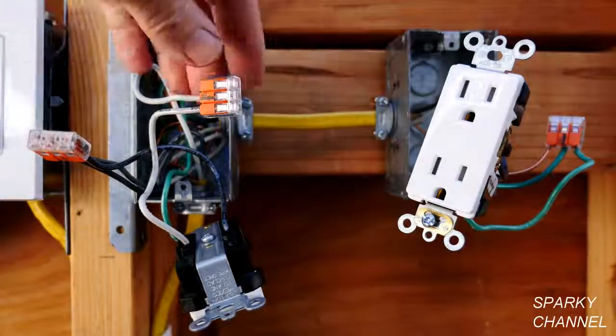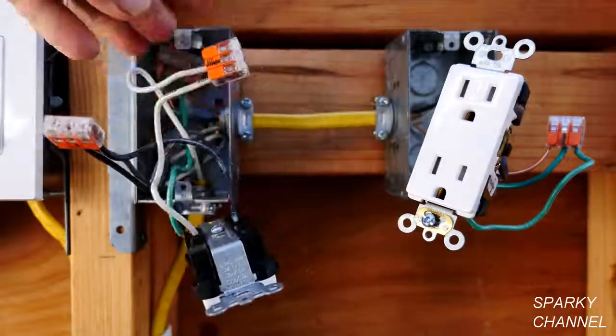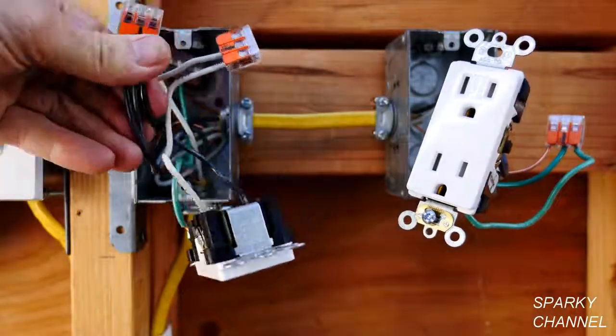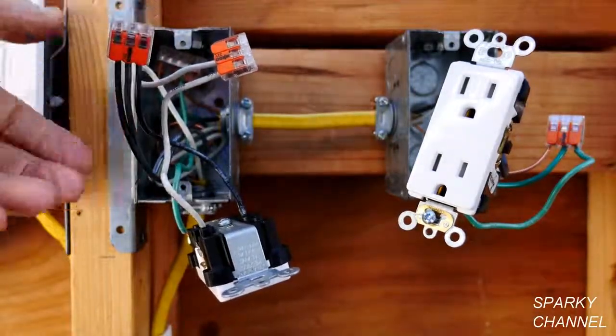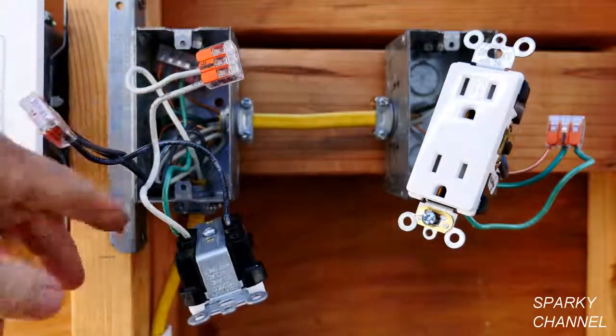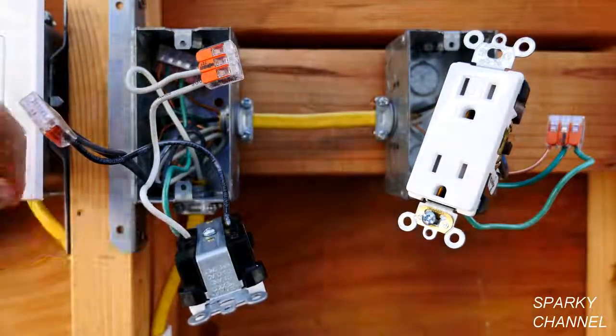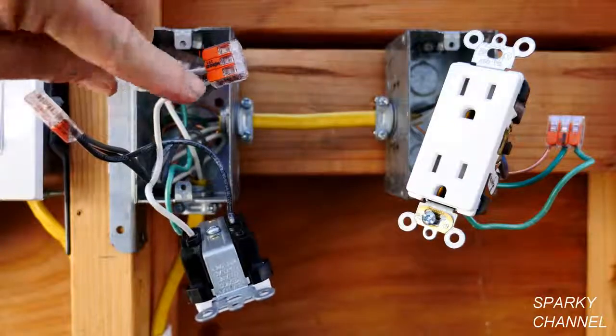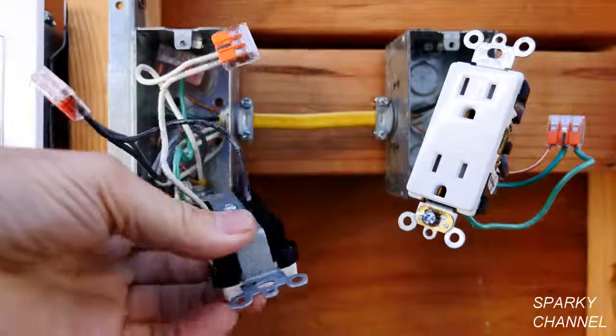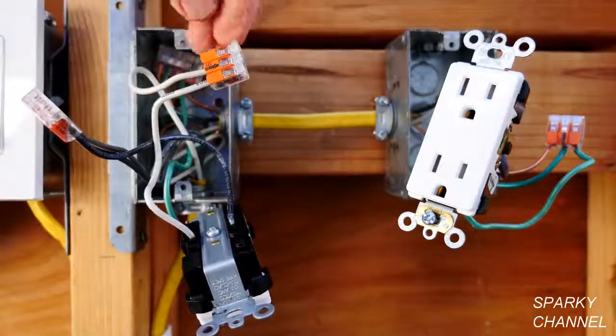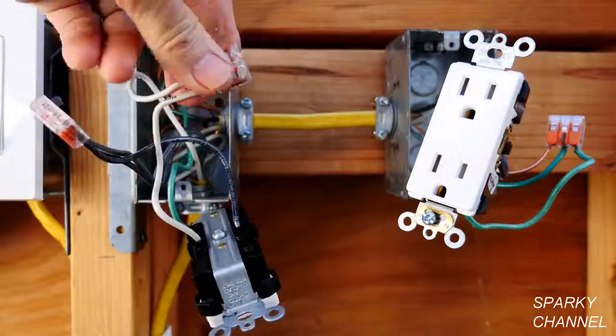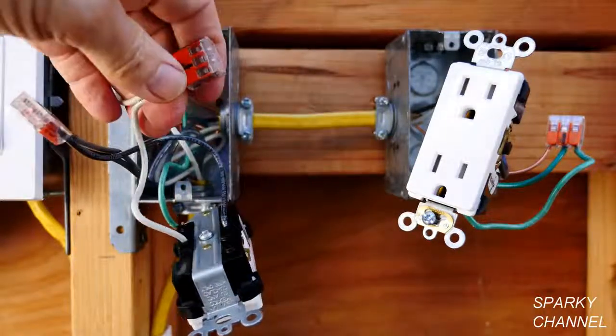Okay, now let's look at the neutral wires. We should have the same as the hot wires, being that we should have one neutral wire coming from the source, the power source, one pigtail going to the receptacle and one going over to the other receptacle, but we only have two in the connector. So let's pull it.